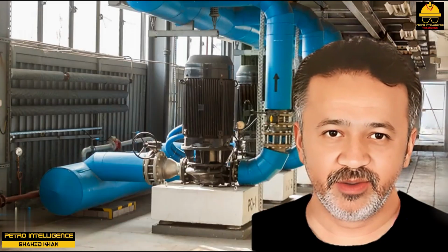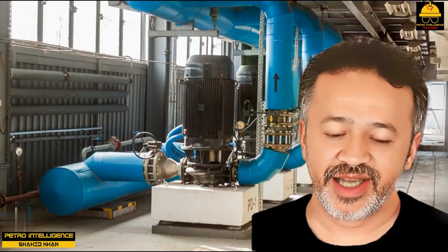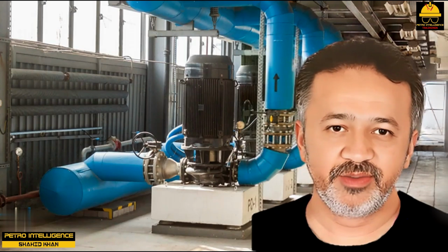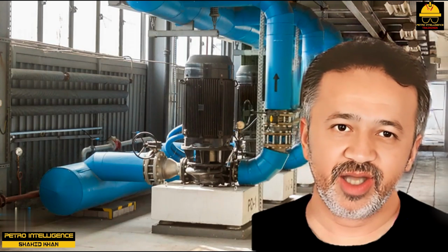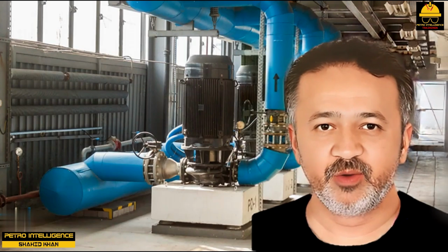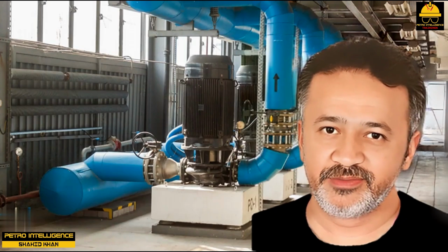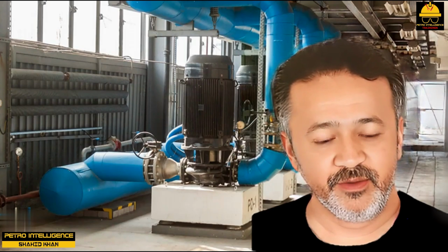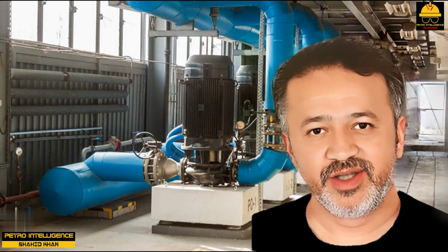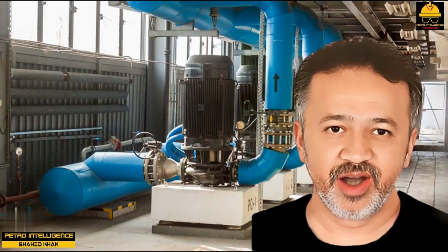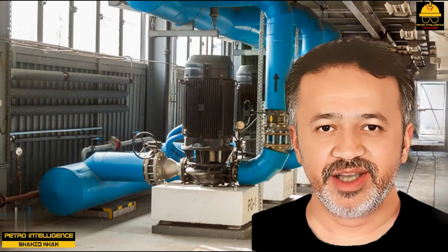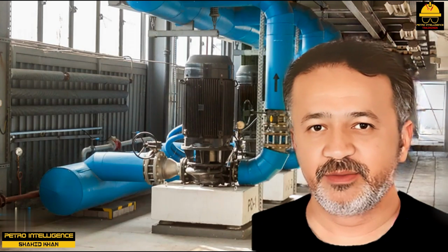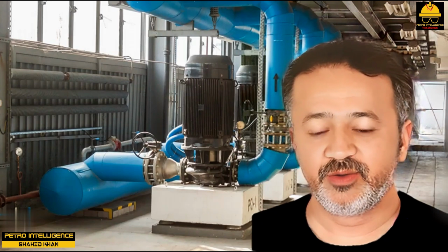I invite you to compare my washing machine story to the accident at the Siberian hydroelectric plant. The lesson is that when we have fluid flowing in a very long pipe or channel, we have to consider what will happen when the fluid flow suddenly stops. We do not want the momentum to be converted into pressure, but into compression of a vapor or into potential energy. For example, on a long crude oil transportation pipeline, we might have periodic surge drums located along the line to safely accommodate a sudden stoppage of the flowing crude.